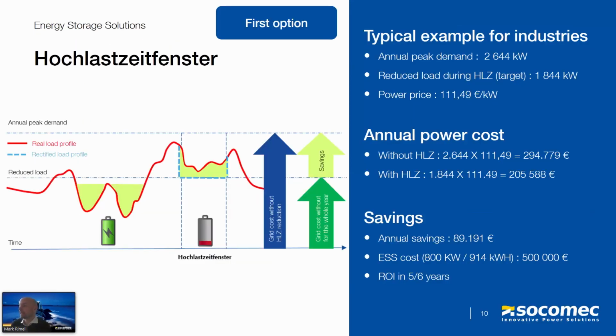Here we have a typical example of a consumer and how a battery storage system can help to provide a return on investment using the Hochlastzeitfenster incentive scheme. So here, if we have a typical industrial customer with a peak of 2,644 kilowatts per year, during the Hochlastzeitfenster period we are targeting to reduce our consumption by 800 kilowatts. So to reduce this consumption to 1,844 kilowatts. We have a power price of 111 euros per kilowatt.